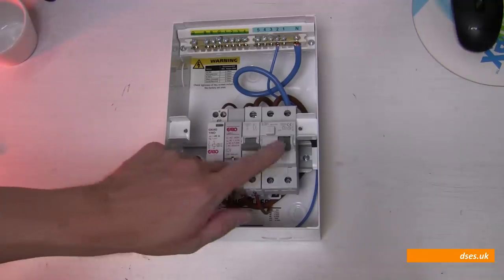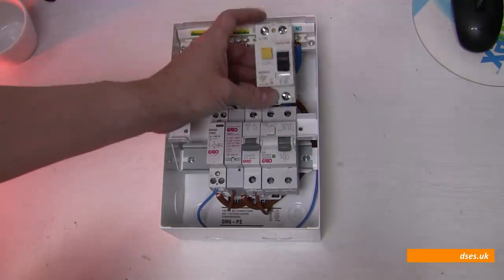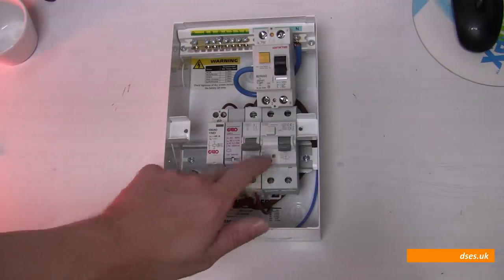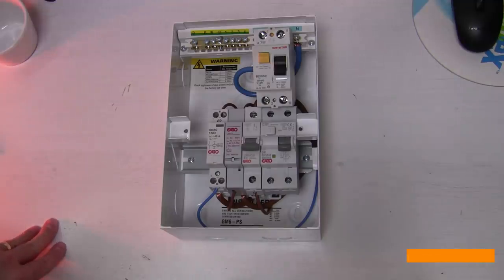The video is linked in the description. Another thing to note about this RCBO is its dual width form factor. Last month I uploaded a video about a Contactum RCD which on the face of it looked to me like an RCBO because of the B25 designation on the front. In fact, here is said device. Although it's got that B25 on the front, a closer look at the BSEN number confirmed it was a device to BSEN 61008 and not 61009, therefore it provided no overcurrent protection. Some commenters on that video said the dual width form factor was a dead giveaway, but I'm told this dual width form factor is popular in Europe for RCBOs. This Garo model is to BSEN 61009, therefore when it says B40 on the front, we know it's a B curve rated at 40 amp for overcurrent protection, as well as providing additional protection of up to 30 milliamps of leakage current — unlike this rogue Contactum which says B25 but is not a B curve and provides no overcurrent protection. Naughty naughty.